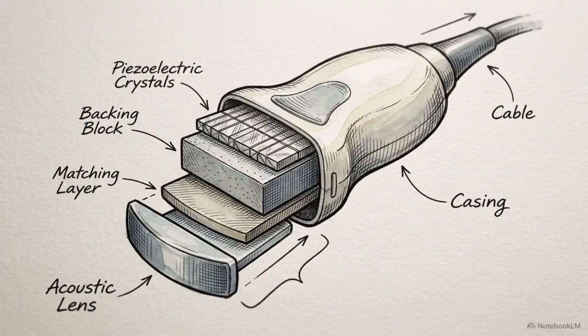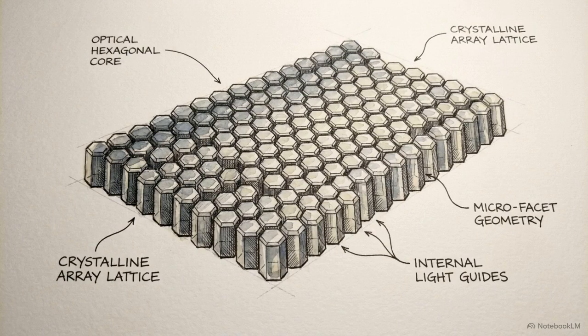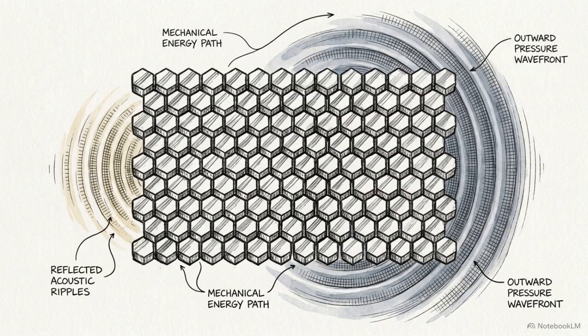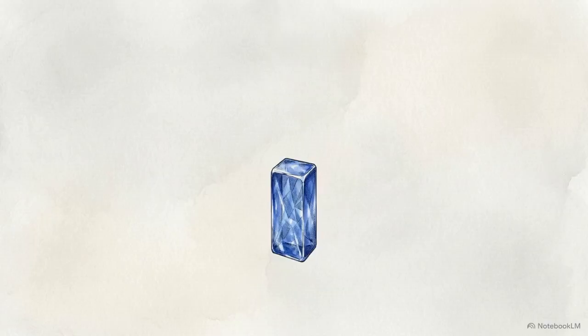Peeling back the casing of the external transducer reveals 4 distinct internal layers, each built to strictly governed geometric dimensions. The core component is the piezoelectric material. In a standard probe, this layer is composed of an array of 256 individual crystals. These crystals are responsible for both sides of the acoustic exchange, generating the initial ultrasound wave and receiving the returning mechanical echoes. This diagram isolates the piezoelectric layer to show its structural requirement.